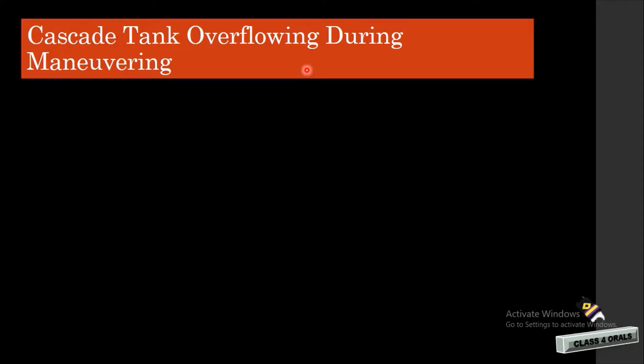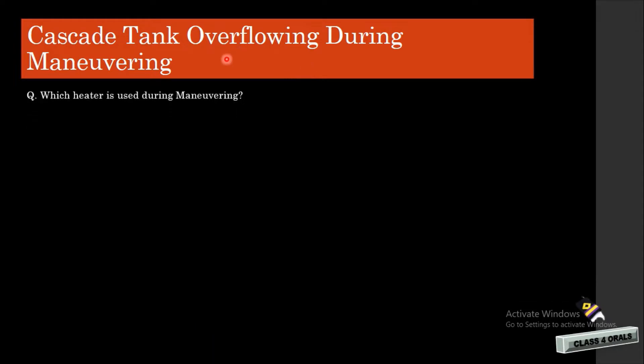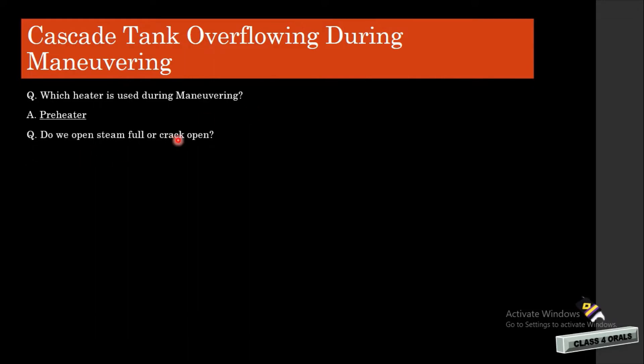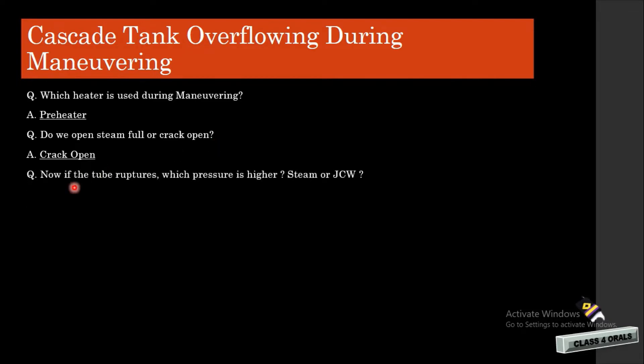First of all, we are taking the reasons of cascade tank overflowing during maneuvering. The question is: which heater are we using during maneuvering? It is the preheater. Do we open the steam fully or crack open? It is crack open. But suppose the tube has ruptured in the preheater.